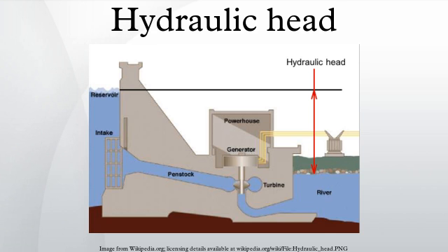The static head of a pump is the maximum height it can deliver. The capability of the pump at a certain RPM can be read from its QH curve. Head is equal to the fluid's energy per unit weight. Head is useful in specifying centrifugal pumps because their pumping characteristics tend to be independent of the fluid's density. There are four types of head used to calculate the total head in and out of the pump.